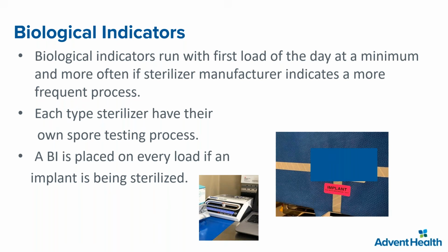So a biological indicator is also placed on every load if an implant is being sterilized. Here, for instance, you can see a picture that says implant. That means that tray has an implant inside that is going to be used in a patient, and we need to guarantee that everything inside that tray is completely sterile, because that implant is going to stay with the patient forever. Okay. And this is the incubator that we use.